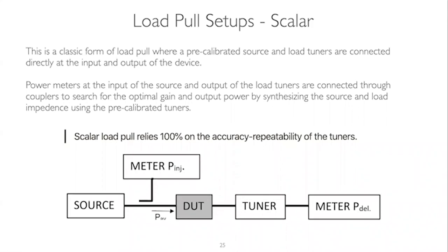And then you have to rely on the calibration of the tuner to be able to de-embed. As you move, the tuner will present different impedance, but also have different loss. So when you measure the output power at the power meter, you need to de-embed the insertion loss of, say, attenuators and whatnot. But what's more important is the tuner, as it's not only taking care of the impedance, but also changing the overall loss per impedance.